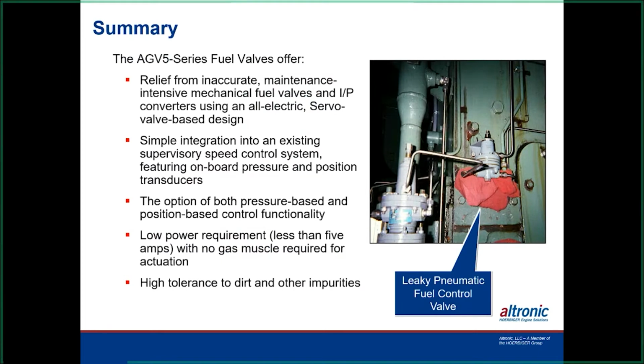So the idea of trying to get a good stable engine when you have all these parts moving around is not a practical way of doing it. With the other valve, the AGV5, it would bolt in the same area, and then you run a 4-20 right to the valve. So any kind of adjustments the panel is making, you get immediately at the valve. It's a very, very good improvement over these older type systems.